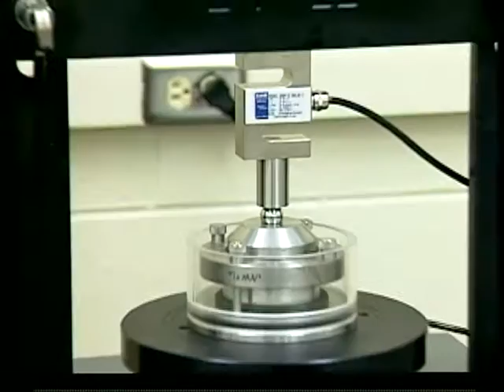I go into view, system, make sure everything is okay here. One quick test which I'm going to be doing tomorrow and checking, I want to make sure that everything is working correctly. So I went to a system monitor just to check that there is a communication, the power is on, limit switches are off, and the sensors are alive and responding. One quick test I always tell people to do is the load. What I do here, I push on the load cell, and I should see about 20 pounds. That's what a normal human being who is not on steroids will push, about 20 pounds. So that's a quick, easy test.